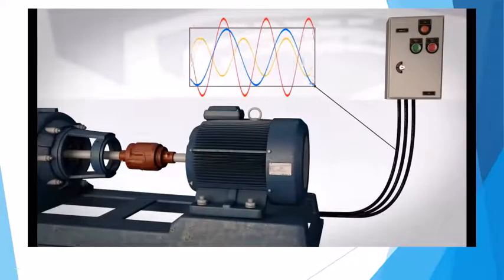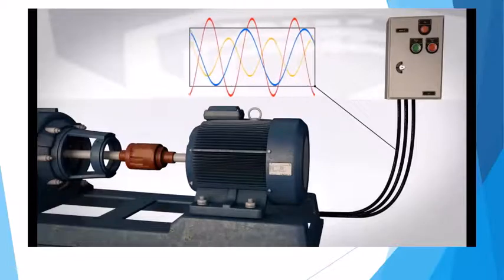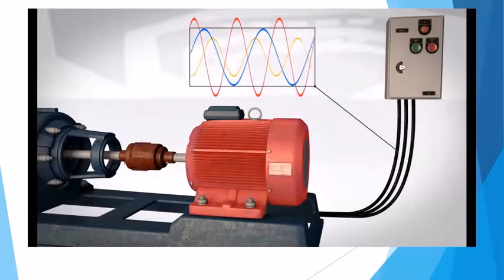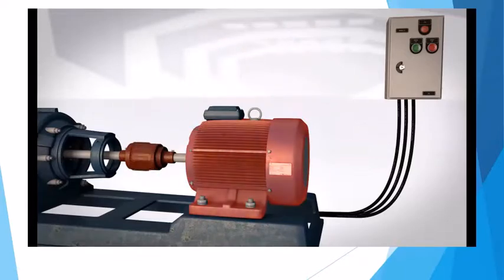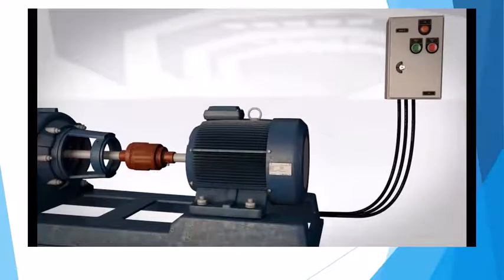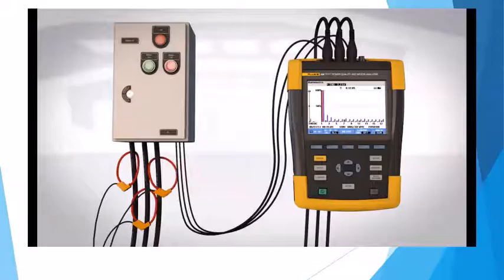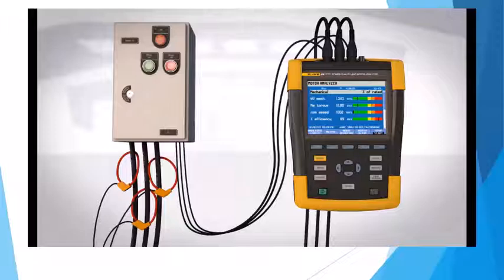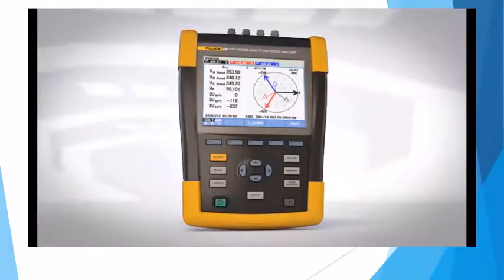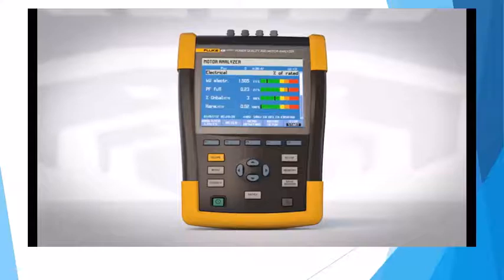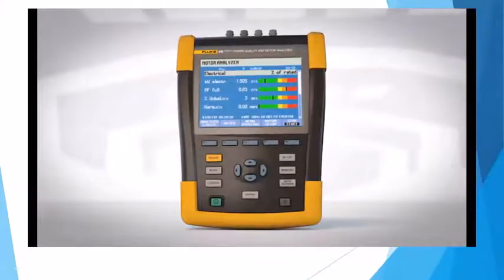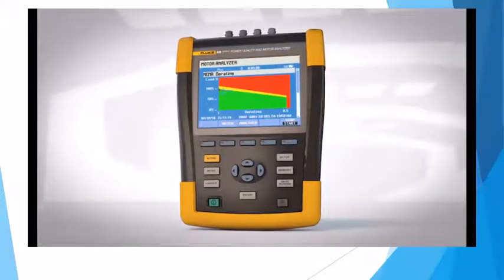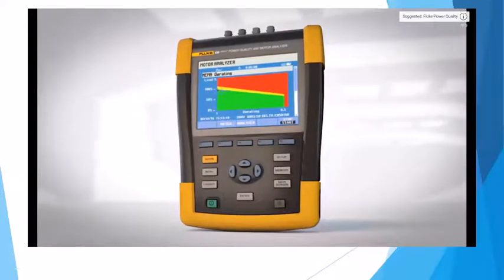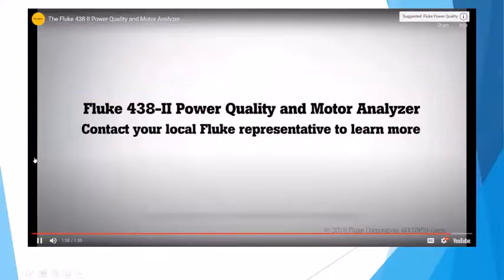Power quality issues, such as unbalance and harmonics, can cause motors to run hot, eventually stressing windings and accelerating failures. Motor failures lead to costly downtime, and the cost of waste associated with inefficient motors adds up. When testing direct-online motors with the new Fluke 438, you get both power quality information and mechanical performance data in the same test with a single tool. With an intuitive user interface, optimized current probes, and at-a-glance motor status screens, the Fluke 438 gives you the motor troubleshooting information you need to make better maintenance decisions and keep your plant up and running. Contact your local Fluke representative to learn more.